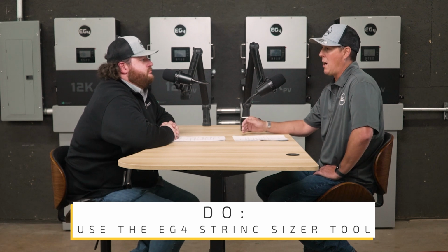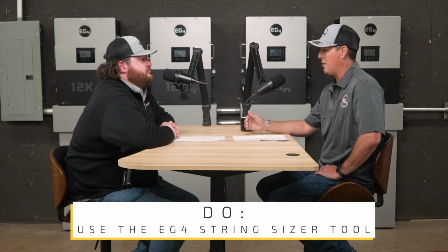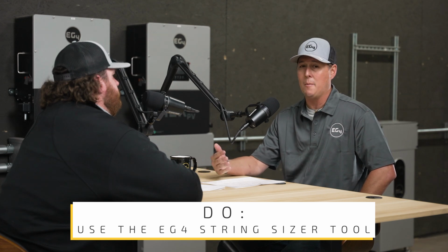And this is just going back to kind of that voltage test, right? We have our string sizer on our website. Go in there, be proactive, right? When you get your plan sets back from your design system and you've got that PE stamp, go back and review it. If you don't know how to do that, please reach out to somebody on our team. We're happy to go through it with you, teach you how to use that string sizer accordingly. So that way we're making sure that you are giving your homeowners the best possible outcome for their system to be functional. For sure. In that string sizer, there is an opportunity in there to select the panel type that you're utilizing. You go in and put in your highest rated temperature, your lowest rated temperature to make sure that during a low temperature situation, your voltage rise doesn't increase above that 600 volts DC. Yeah. So utilize that string sizer.